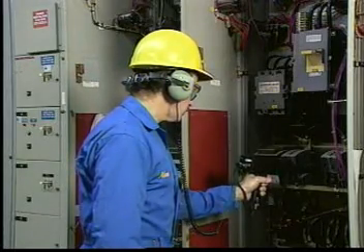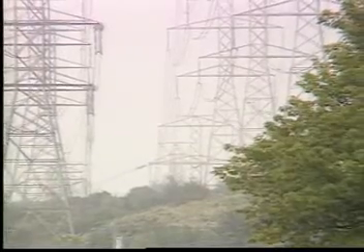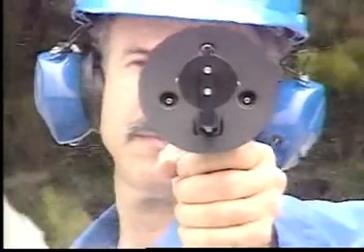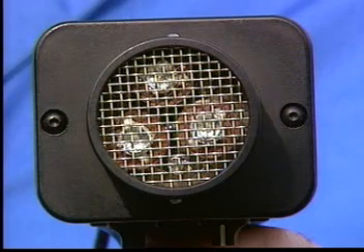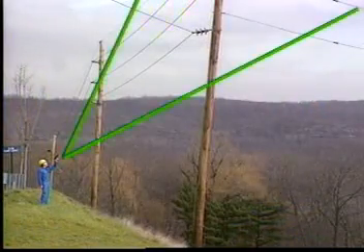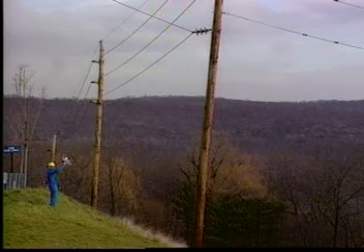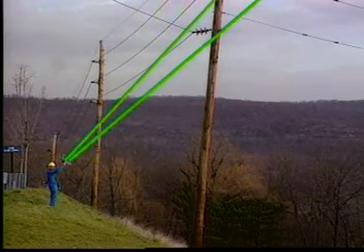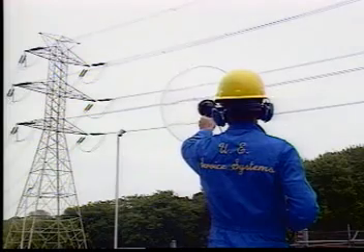Once the leak has been located, you may investigate further using other complementary technologies. For some situations, more advanced Ultraprobe techniques are required. For testing high-voltage equipment at a safe distance, the parabolic reflector is used. The standard Ultraprobe scanner — the patented trisonic scanning module — has three transducers and its field of detection tends to widen with distance. The parabolic reflector has seven transducers, making it a powerful add-on for special-purpose and long-range testing. It has a very tight, narrow band of detection, making it extremely directional, and its special shape and sighting mechanism enables users to locate an exact trouble spot at distances exceeding 200 yards.